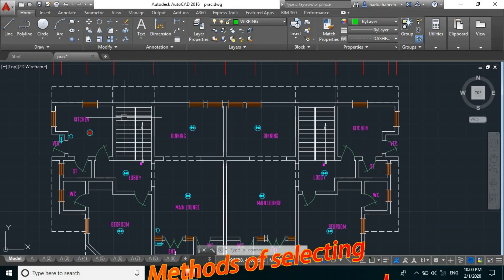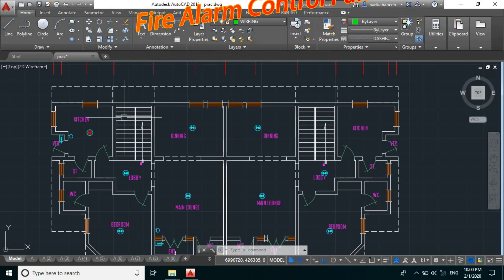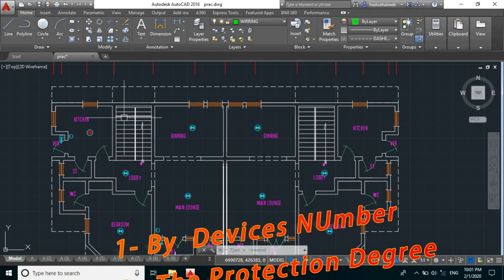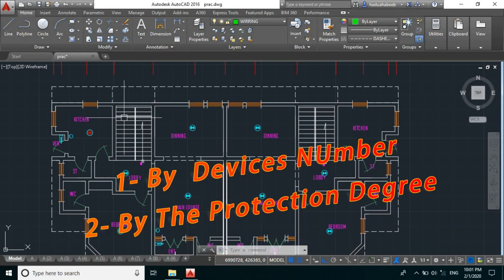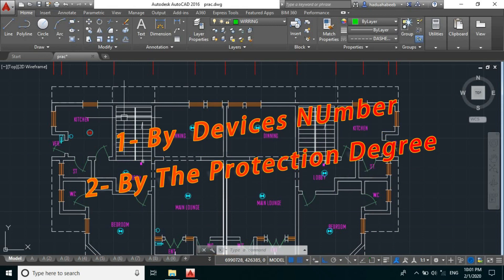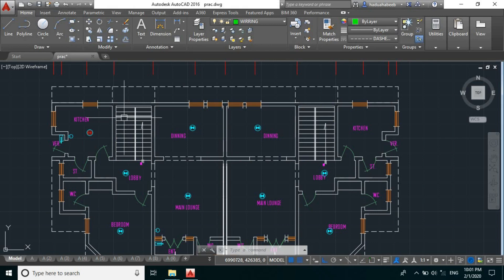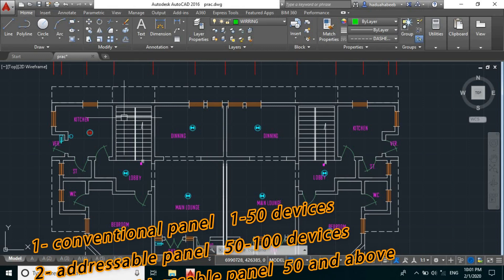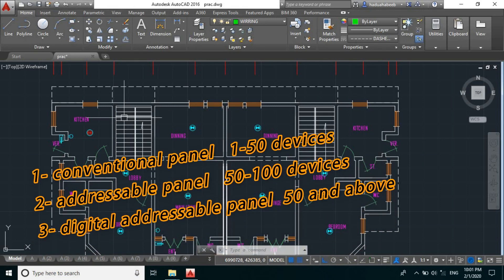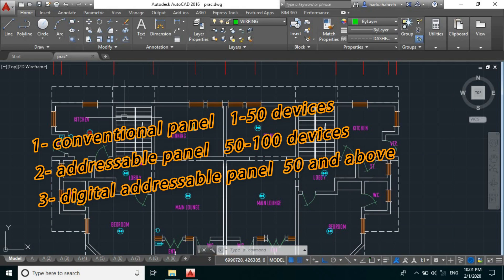We have two ways of selecting the type of control panel to use for a project. The first method is by numbering method — meaning the number of sensing devices. The second method, which is more professional, is the degree of protection method. With the numbering method: if the number of sensing devices is less than 50, we use a conventional system; if between 50 to 100, we use an addressable system; and if greater than 100, we use a digital addressable fire alarm control panel.